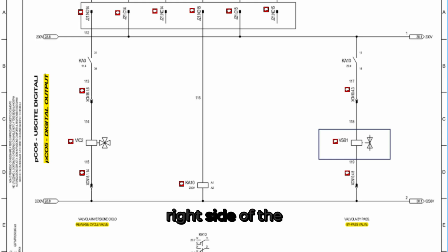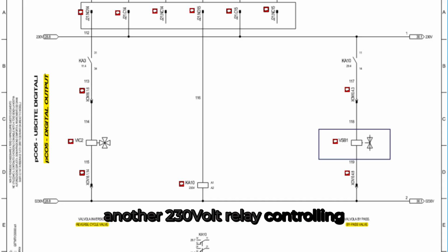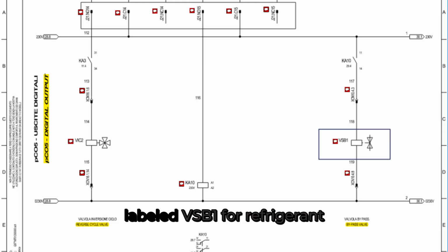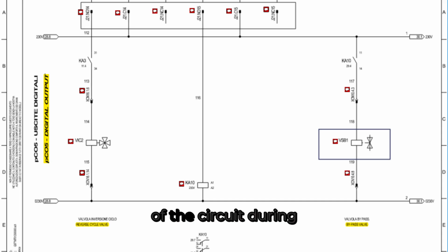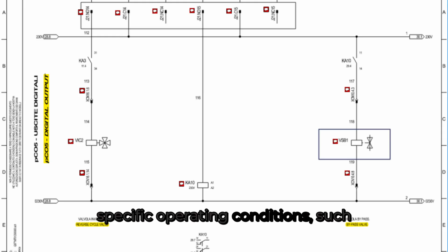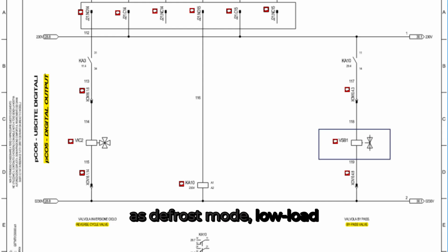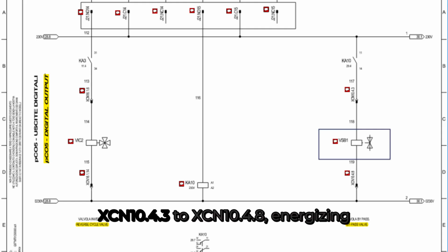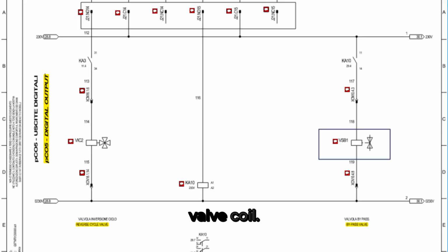Now moving to the right side of the page, we see KA10, another 230-volt relay controlling the solenoid bypass valve, labeled VSB1, for refrigerant circuit 1. This valve allows refrigerant to bypass certain parts of the circuit during specific operating conditions, such as defrost mode, low load operation, or system equalization. When KA10 closes, voltage is sent through terminals XCN 10.4.3 to XCN 10.4.8, energizing the VSB1 solenoid bypass valve coil.